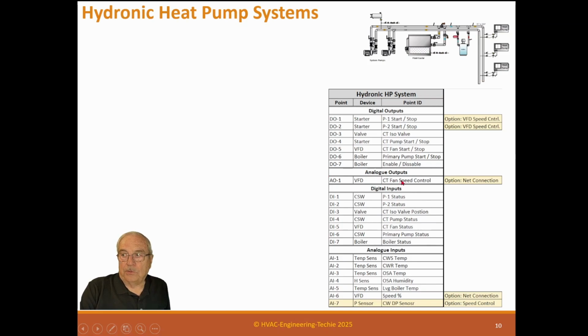The analog output is the cooling tower fan speed control, just like the other one. The digital inputs are a current switch on P1 and P2 to tell if they're actually running loaded. DI3 is a valve position, so we have position switches on these. A condenser current switch on the pump status on this one to make sure it's running. VFD fan status; we're doing fan status off the VFD. A current switch on the primary pump status, which is this primary pump in the boiler. And then we have a boiler. We start and stop this boiler in the panel. Now the boiler has its own internal temperature controls. All we do is enable the boiler or disable the boiler and let it run.